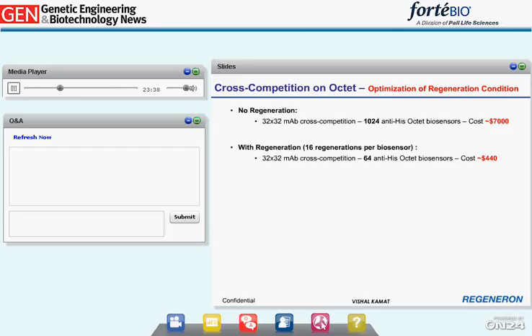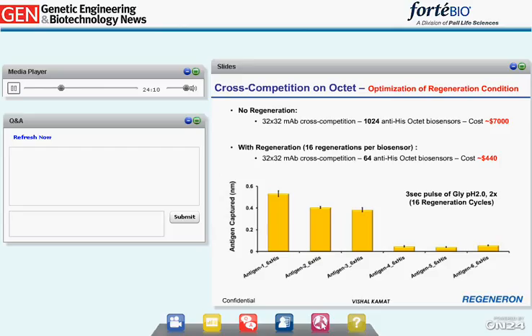If we were able to regenerate the anti-penta-HIS biosensor 16 times, the total cost of running a 32-by-32 cross-competition would be reduced to around $440. We screened different regeneration conditions using different antigens and found that two regenerations of glycine pH 2.0 for 3 seconds each would completely regenerate the surface without affecting the binding capacity of the anti-penta-HIS Octet sensor. Even after 16 regenerations, the binding capacity of the sensor remains the same. We now routinely use this regeneration condition.